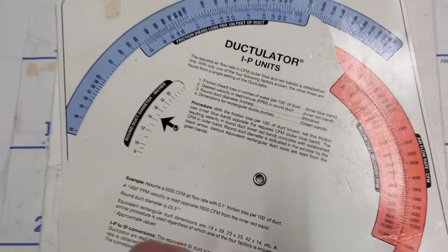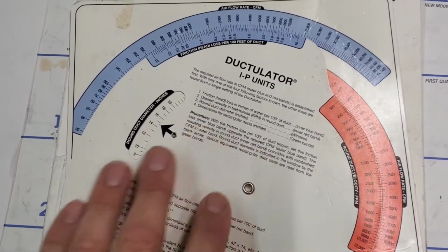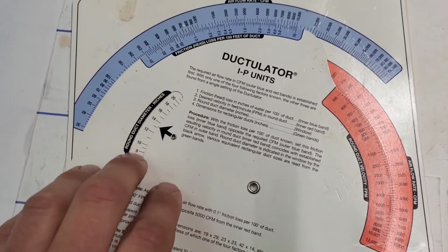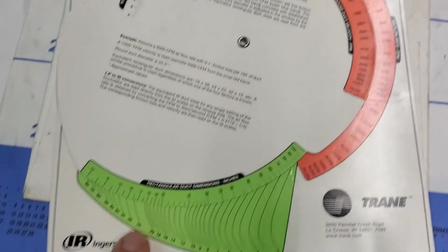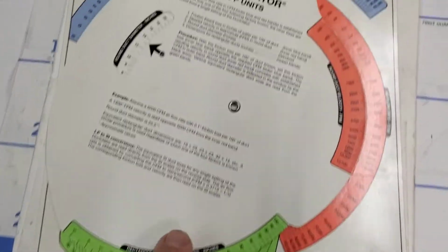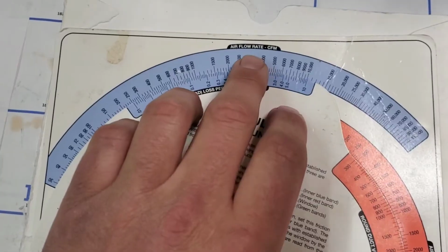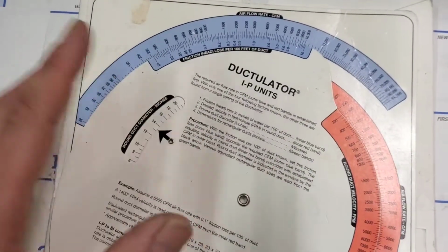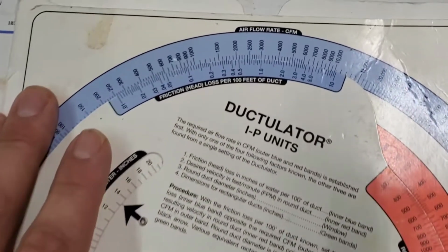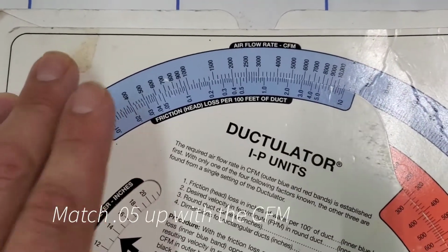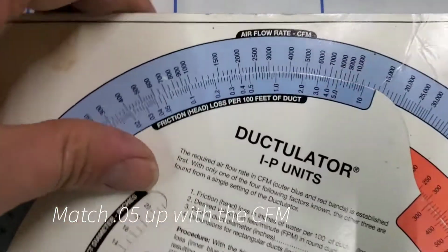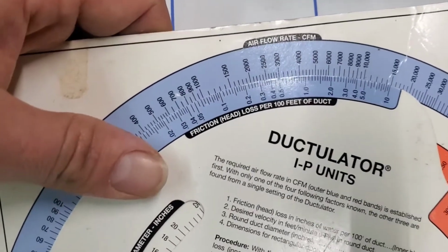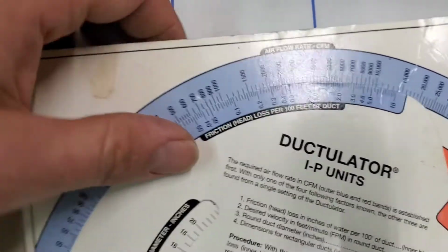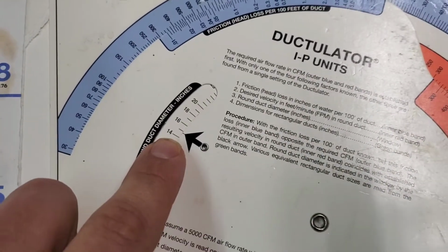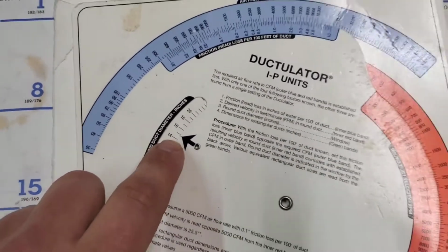So this is a ductulator, and I've got a video on how to use this. Definitely go check out that video if you want to learn more. But I've got round duct diameter in inches, and then I've got rectangular duct dimensions. The gist of this is I match the CFM, which units are rated at 350 to 400 CFM per ton. So I'll basically go to, hey, I want 800 CFM, which is 2 tons, because 400 twice. I'll match this up, all right? And then I go down here, and round duct says 15. So that would be what I'd need for a 2-ton unit. Gotta have a tape measure.